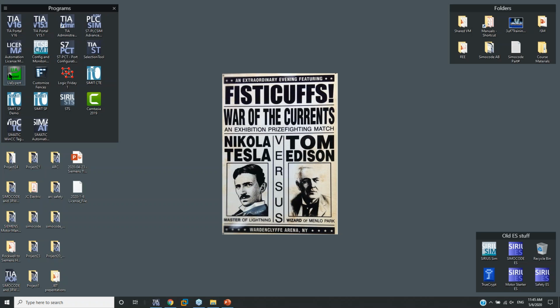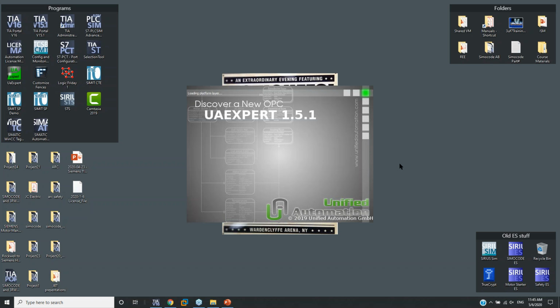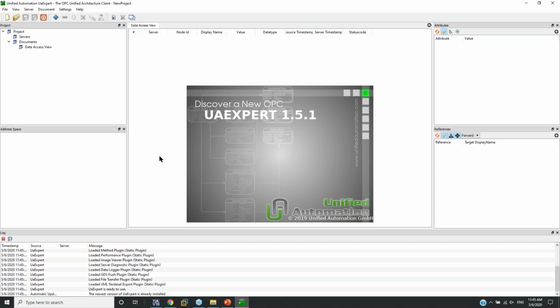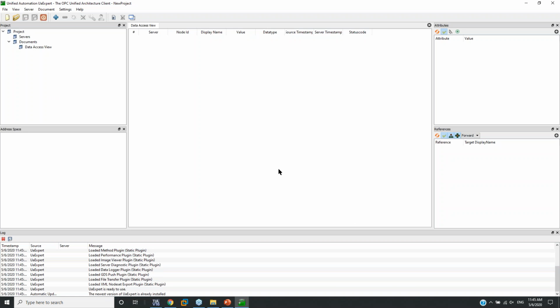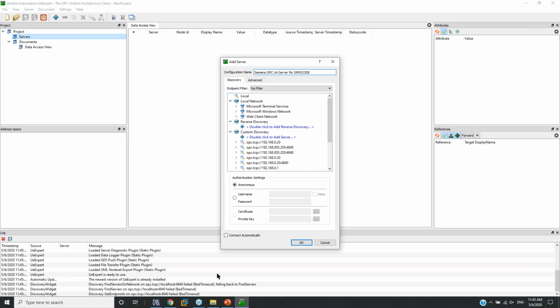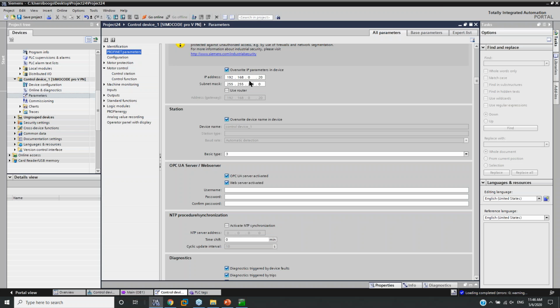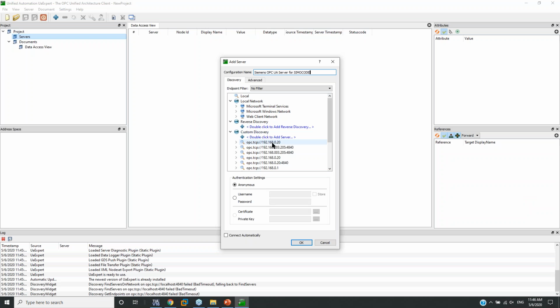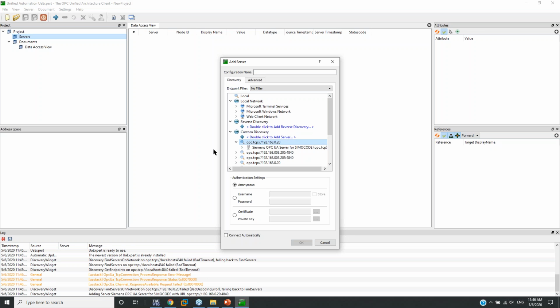Let me get to my desktop, and it's called UA Expert. Let me open that up. This is an OPC UA client. So I'm going to go to servers, right click, hit add. And if you remember on my software, my SIMOCODE was 192.168.0.20. So I'm going to go here. I'm going to say, hey, I need you to go look at that address and look for an OPC UA server. And there it is.